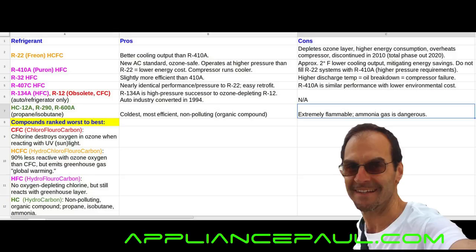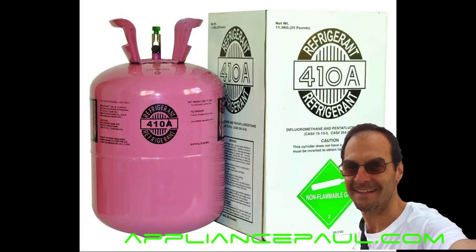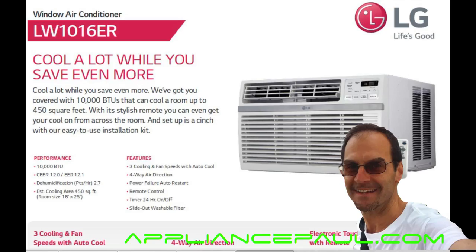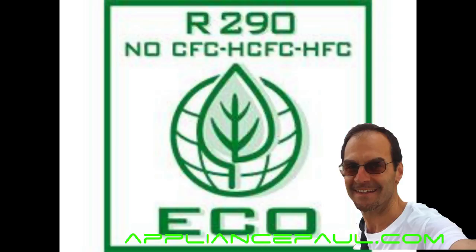The successor to the HCFCs is, in most air-conditioned units you'll buy today in 2017, either the R410A or the R32. These are both HFCs — in purple — which stands for hydrofluorocarbon. Note the absence of the chlorine molecule in this compound; they do not deplete the ozone layer, but they still react with the greenhouse layer to some degree. This LG I was just researching is using R32, and that's also going to be phased out within the next 10 years as we move towards non-polluting organic hydrocarbon compounds.